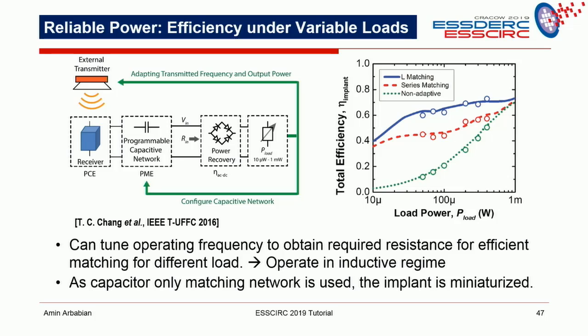Now if you take a sort of class A operation, quote unquote—if you take an implant optimized for a milliwatt, the efficiency is pretty good, look at the green graph here, decent efficiency. Now take the same implant and operate it at 10 microwatts, and the efficiency is horrible. This is similar to a class A operation in designing a power amplifier, because we're not changing the resonant frequency or the load impedance, it's all the same. We just have lower usage on the receiver side.